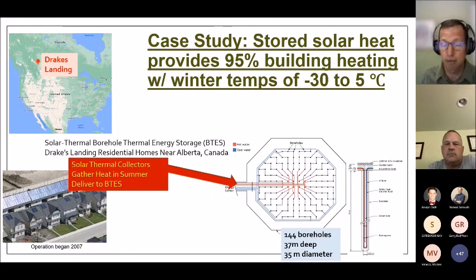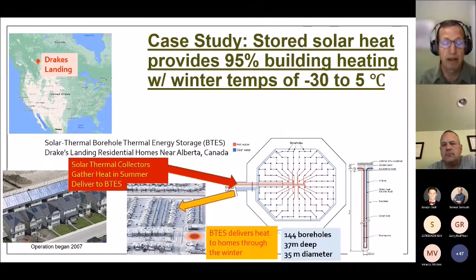The way it works: they have solar thermal collectors on top of the buildings, and in summer and on warm winter days they take that excess heat and put it into the ground, into the BTES. Then when winter comes, they pull that heat out and circulate hot water through the buildings to heat them. I've drawn a little cartoon here showing where the BTES is and about how big it is—it's very small relative to the number of buildings it serves. This particular one is about 120 to 150 feet in diameter and about the same depth.